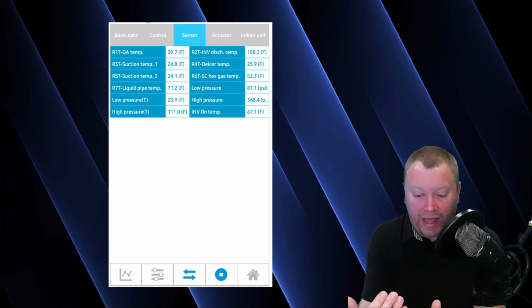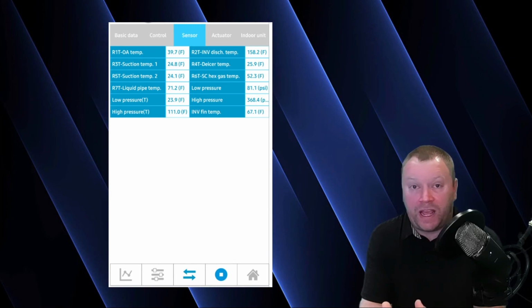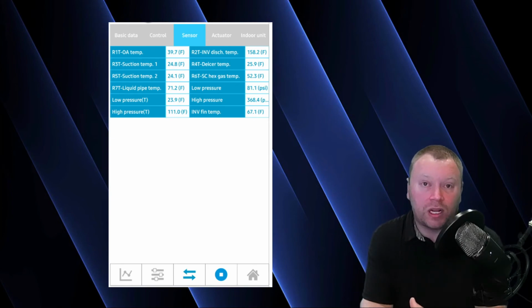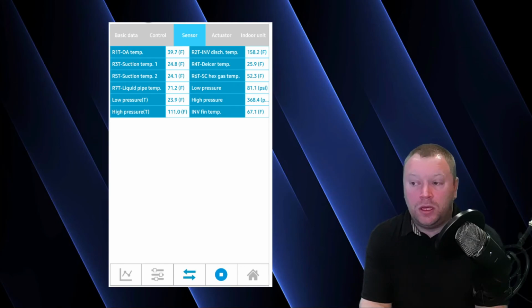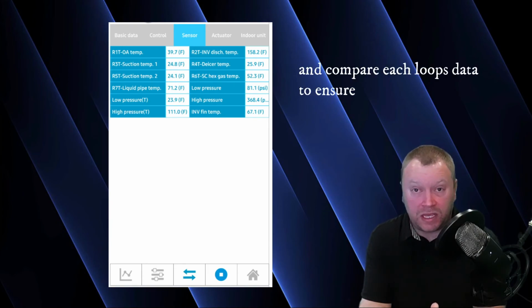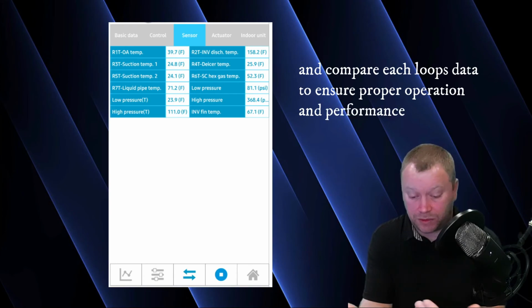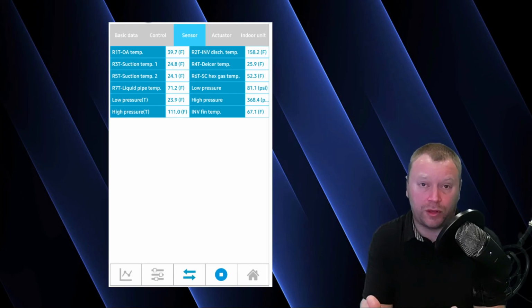It's going to have bad data for a few minutes before it really starts meeting its targets and having good superheat and subcool values. But again, I don't like just showing you good data, because we need to be able to recognize when there's a point that isn't doing what it's supposed to be doing. So once we get back to the compressor, then what I would do from there is make my loop again. And after I get through my next loop, I would make my loop again and again and again. And I basically just keep doing this for the entirety of my recording.